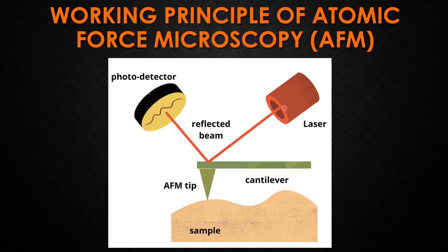The tips are made from silicon compounds with a tip radius of about 10 nanometers. The photodetector records the changes to the reflected laser beam position which is proportional to the movement of the cantilever. Finally, a detailed topographical image of the sample can be captured by scanning across the surface of the material.